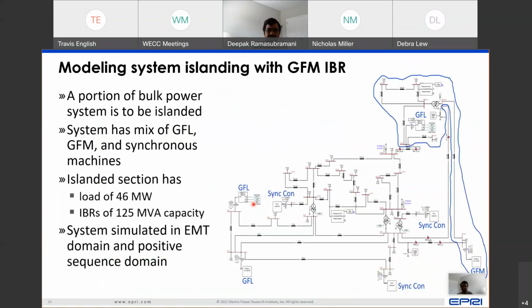So we set up this example study wherein we are using an IEEE test system just so that we can really make the results public. You see that you have a system which has grid following inverters, it has synchronous condensers, it has one grid forming inverter down here, and it has a grid following inverter at the top here. What we want to do is island this portion of the network and split it from this portion of the network, so that the islanded portion has one grid forming inverter and one grid following, and the rest of the system has only grid following and synchronous condensers.